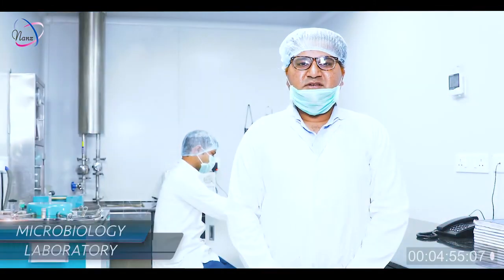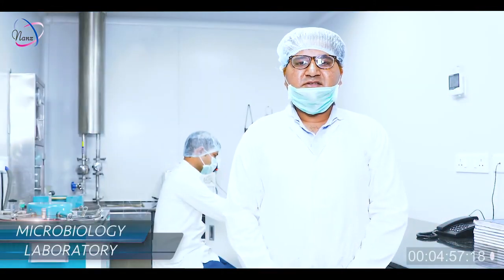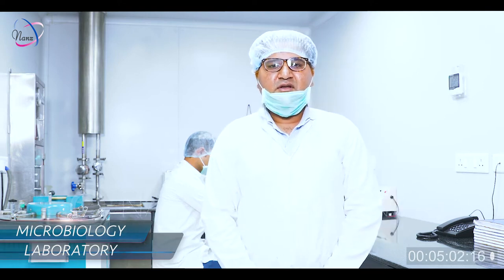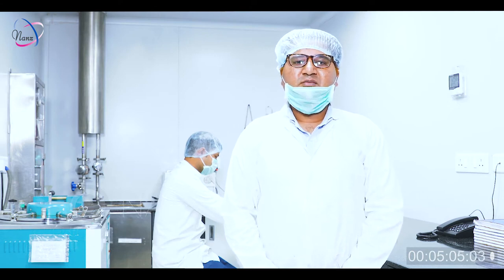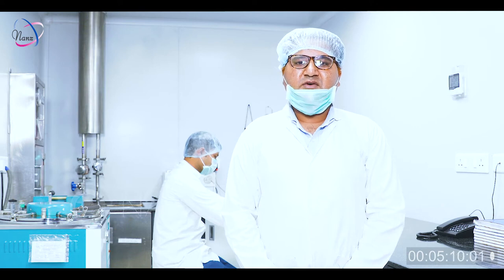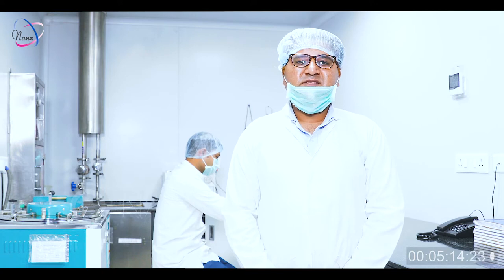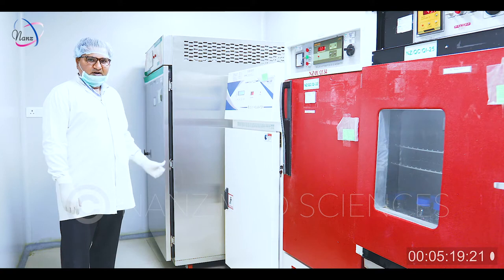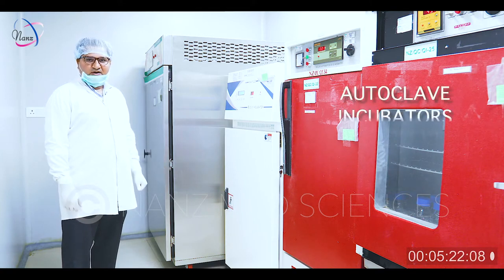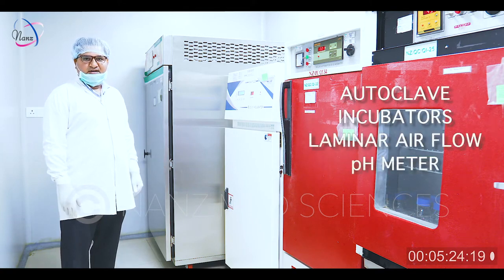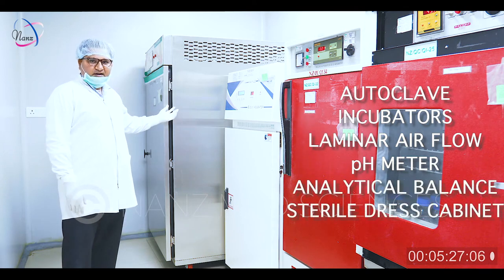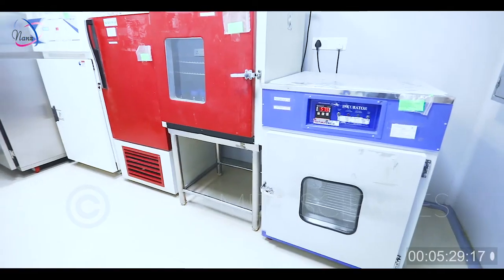Our quality control laboratory is also capable of doing all kinds of microbial analysis in-house as required for raw and finished product testing, water sample analysis, and environment monitoring. A separate area is provided for the microlab. The microlab sections involve activities such as media preparation, media disposal, incubation and MLT testing. The microlab is equipped with autoclave, incubators, laminar airflow, pH meter, analytical balance, sterile dress cabinet and fogger.